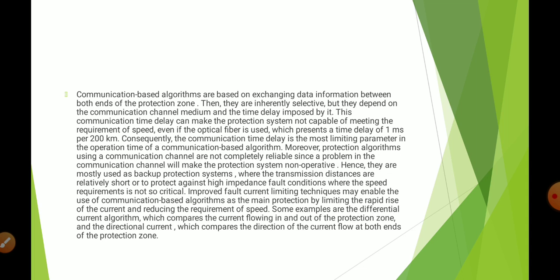Moreover, protection algorithms using a communication channel are not completely reliable, since a problem in the communication channel will make the protection system non-operative. Hence, they are mostly used as backup protection systems where the transmission distances are relatively short, or to protect against high impedance fault conditions where the speed requirement is not so critical. Improved fault current limiting techniques may enable the use of communication based algorithms as the main protection by limiting the rapid rise of the current and reducing the requirement of speed. Some examples are the differential current algorithm, which compares the current flowing in and out of the protection zone, and the directional current algorithm, which compares the direction of the current flowing at both ends of the protection zone.